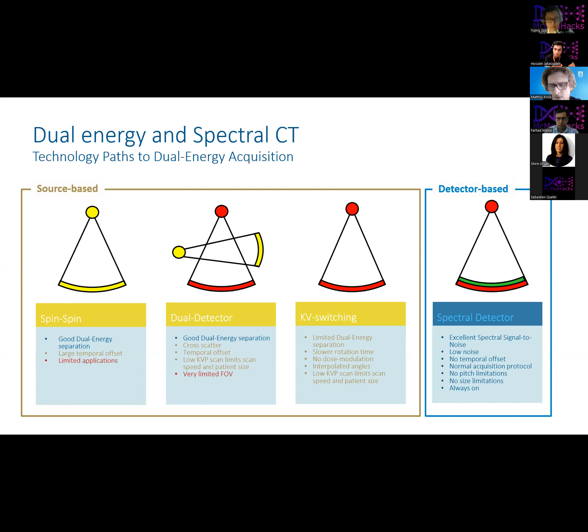The way that it works is as follows. It has two layers of two different materials. First, the low energy photons that are coming in are being detected here by a photodiode. So if they come in, you get the photoelectric effect, and so basically the X-rays are being transferred into light. That's being detected, and that gives you the low energy information.